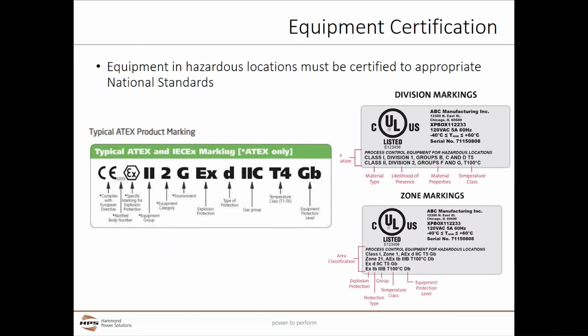In regards to equipment certification, all of the hazardous location equipment must be certified by appropriate national standards. The difference between the three standards that we are offering is in the testing or classification body. Each rating is created by a recognized standard body, with ATEX being European, UL being North American, and IECEx often used for international standards. Your company may choose a specific standard to base their decision on, or base it on the installation location, where it's going to be, depending on what standard is going to be required.